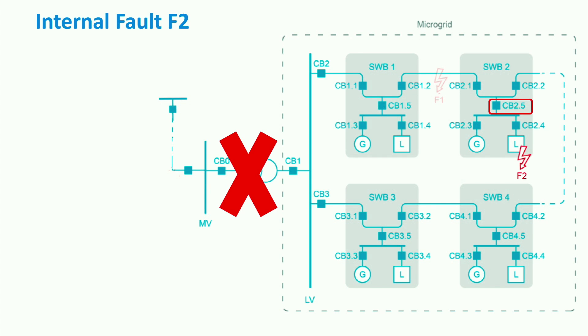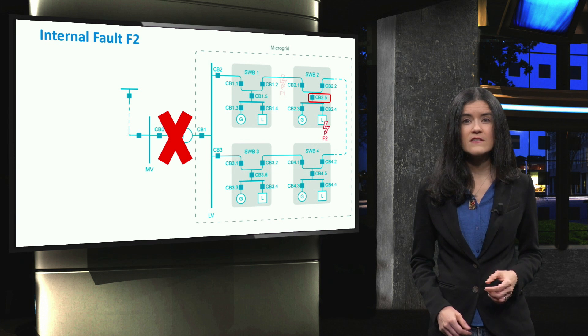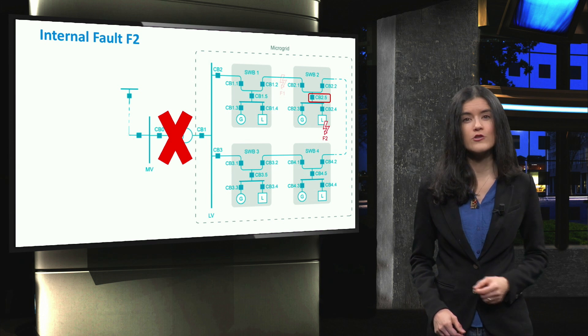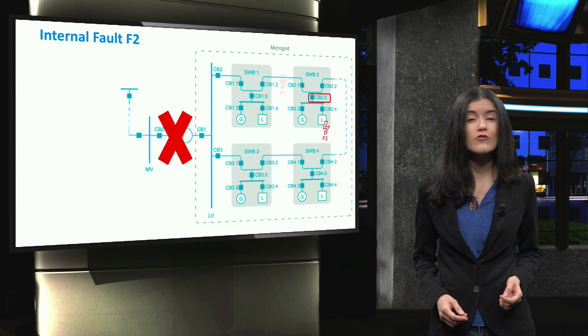It is worth noting that both the protection settings of CB2.4 and CB2.5 can be different during grid-connected and islanded modes of operation, since these two breakers are required to trip at much lower overcurrents during islanded mode.